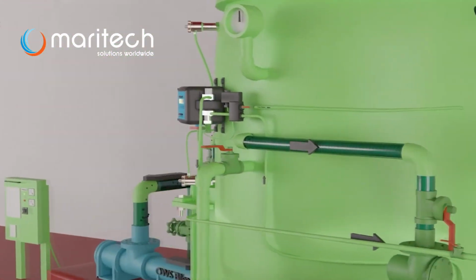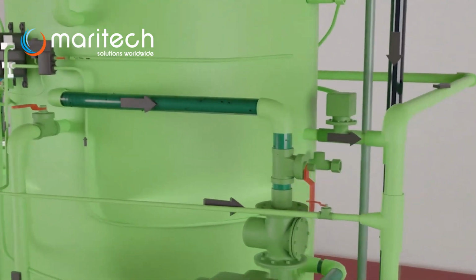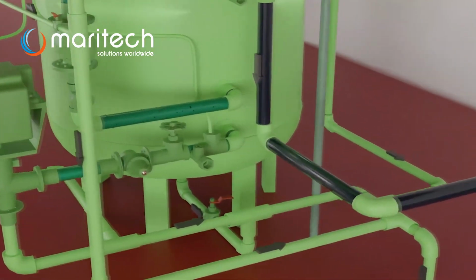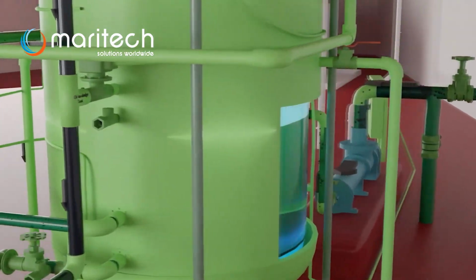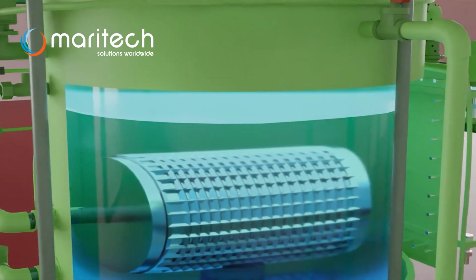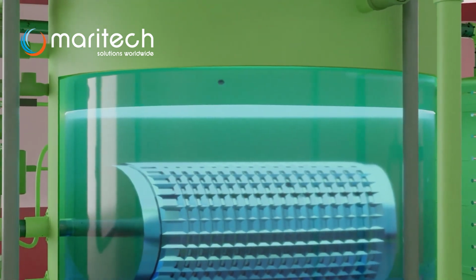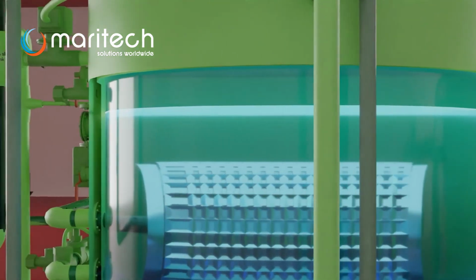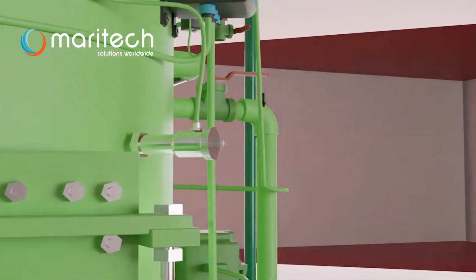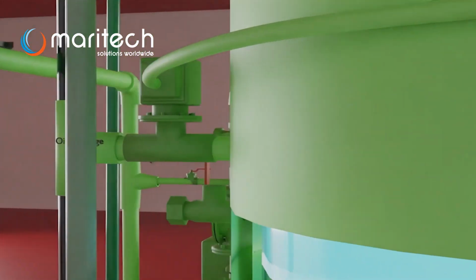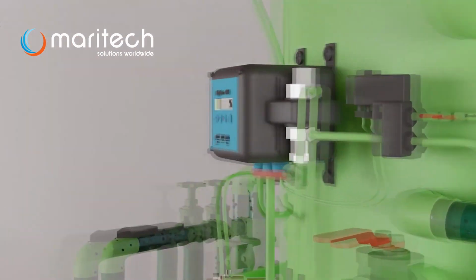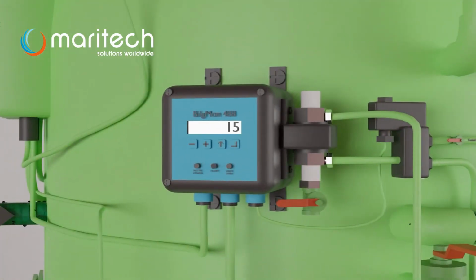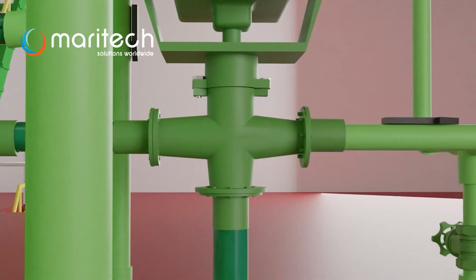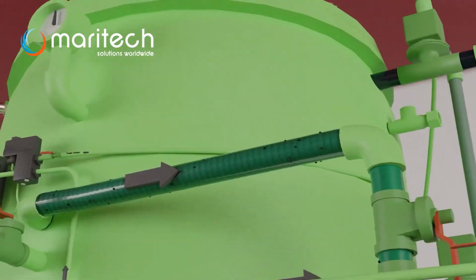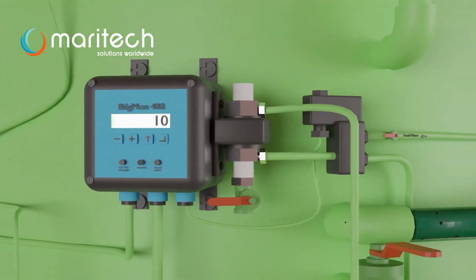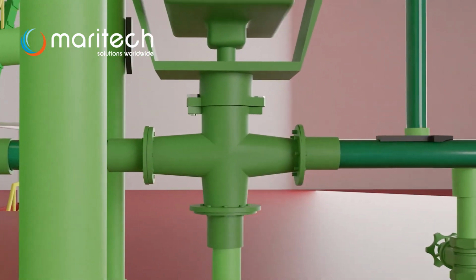Now, we can see what is happening in the secondary chamber. In the secondary chamber, we can see the globules of oil and the finer oil particles, which were not separated in the primary chamber, rise and collect on top. When the oil level probe detects oil, it opens the oil discharge valve, directing oil to the sludge tank. If the oil content meter senses over 15 ppm of oil, it closes the discharge to the overboard. Once the oil content is below 15 ppm, the discharge reopens to the overboard line.